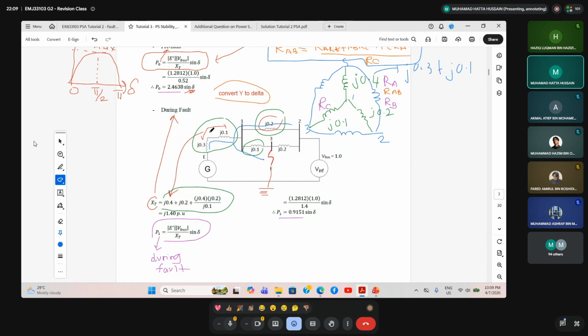Okay, you just compare the power angle equation before pre-fault and during fault condition. We can see that the power magnitude is reduced, right? It's reduced from 2.4638 going to 0.9151 per unit. Nampak tak? Dia turun kan? Dia reduce. Let's say if you get an answer bigger than 2.4638, it means you already made a mistake when converting from star to delta connection.